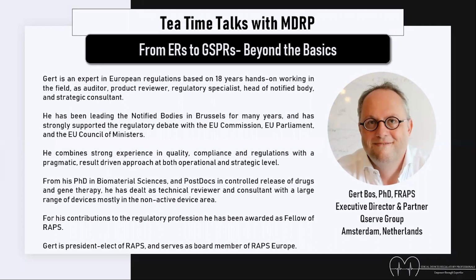During the time I worked for notified bodies, I have been basically speaking on behalf of all notified bodies in my roles as chairman of the notified body fora in relation to the build-up and the negotiations for the MDR and the IVDR. So lots of content from the notified body perception, which of course is logical because ultimately, notified bodies have an essential role in the interpretation between the more vague wording in the law and the practical documentation that a manufacturer is providing. So forming the bridge, that has been very helpful in building a doable, workable MDR, and especially also Annex 1 on the GSPRs. That is pretty technical. So in that sense, it's quite easy for manufacturers to understand what they need to do, provided they understand the concepts behind the medical device regulation.